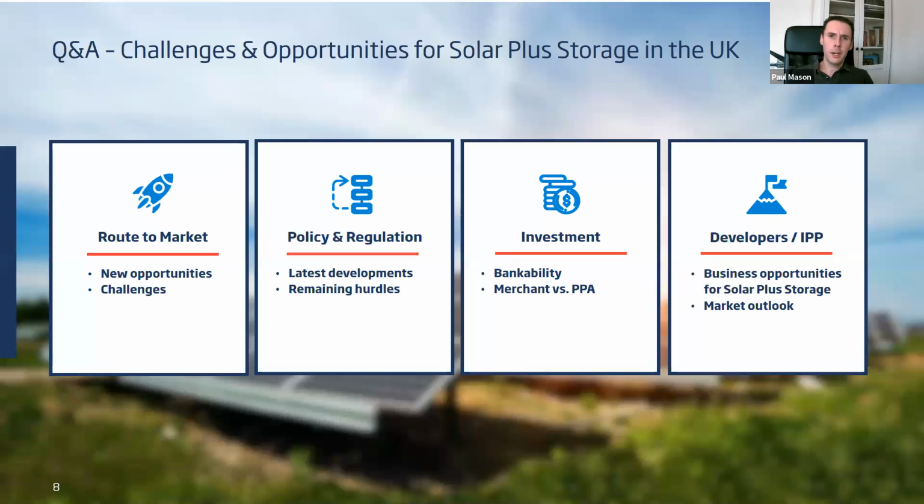So for example, you're looking at, say, EFA block 5, the 3 till 7 p.m. block of time during the winter months, which accounts for less than 1% of your solar income. But it's actually a really lucrative time for optimizing battery storage revenue. So if you gave priority to a battery over that period, you lose less than 1% of your solar income, but boost your battery income by circa 10%. So I think the combination of more real-time procurement, along with evolving attitudes towards which assets are getting the priority on the grid connection, will really boost the investability of this.